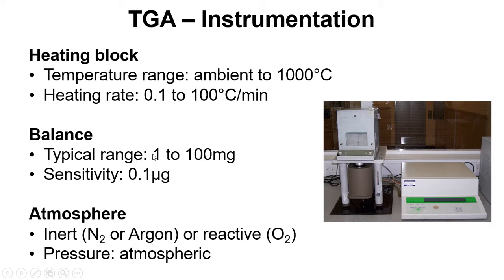The balance typically handles 1 to 100 milligrams for the sample. We have very good sensitivity so we can measure small changes in mass as low as 0.1 micrograms, which is 10 to the minus 6 grams.